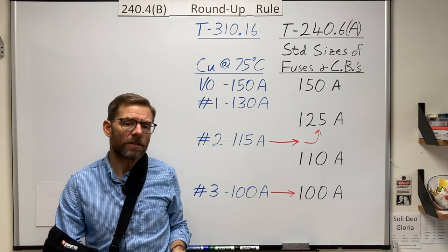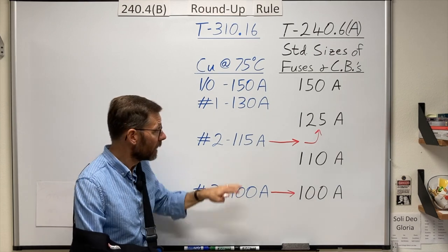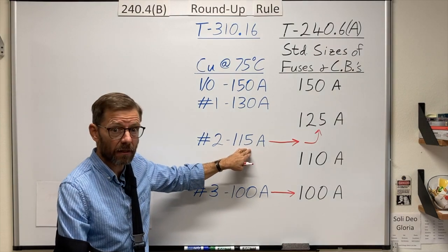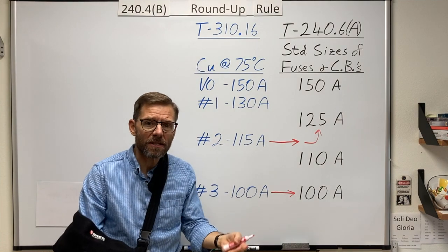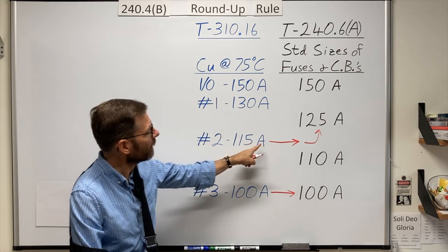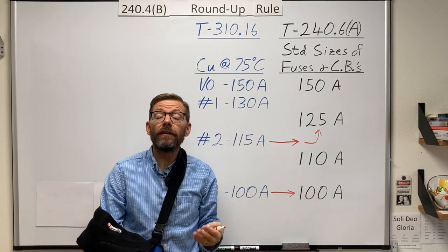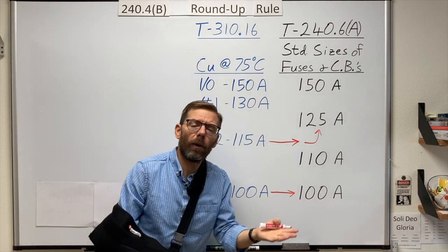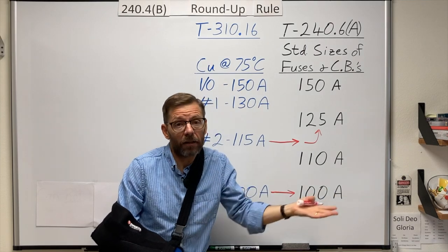What would be a couple of benefits? Well, for starters, I could get my full ampacity out of this conductor. Copper is expensive. I don't want to have to buy more copper than I need to. And also, I could get a little extra wiggle room to avoid nuisance tripping. Depending on what my load's characteristics are, that could be a benefit.